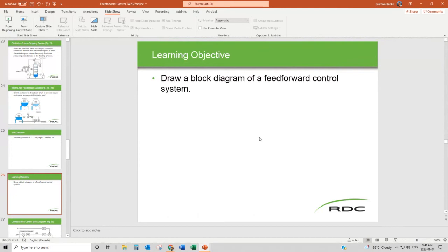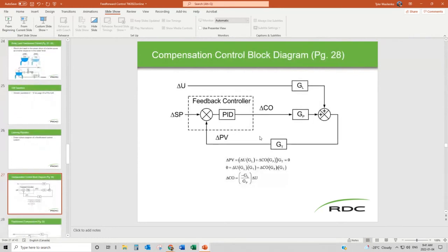Okay, block diagrams, just like third year, block diagrams were a thing. So here's a block diagram of a feedback controller with some compensation here. Then we have our feedback compensation, and we have our load disturbance being measured here as well. So we'll get an error generated by the difference between set point and process variable. And we'll have possibly an error introduced by a load disturbance. They are combined together in this compensation, and that variable is fed back through the transmitter, again, feedback to reduce that offset that would be present if we had straight up feed forward control.